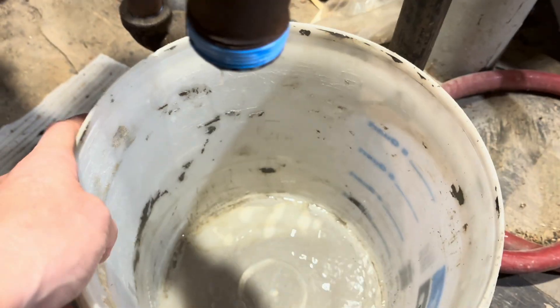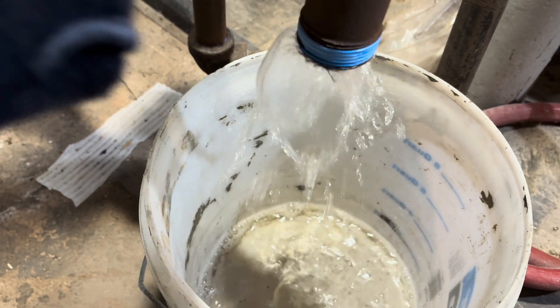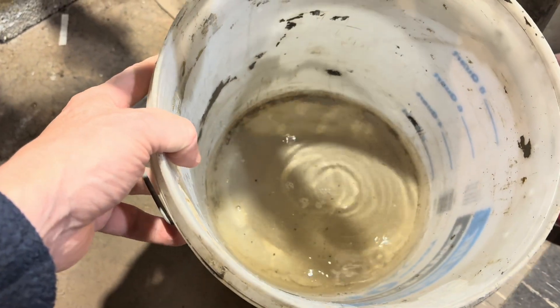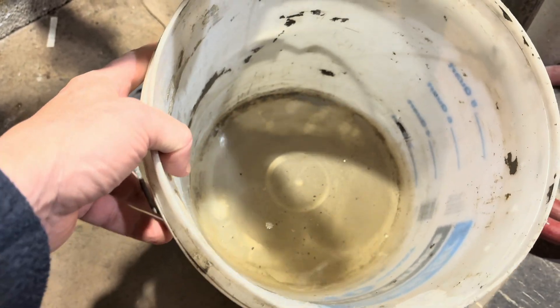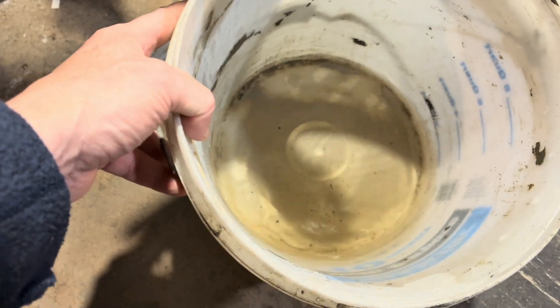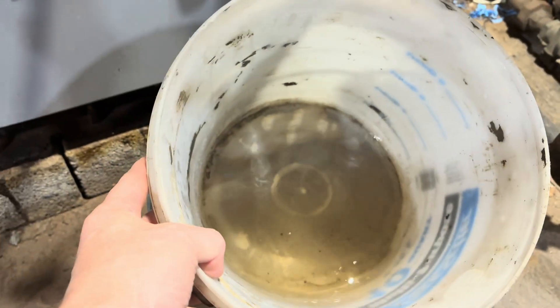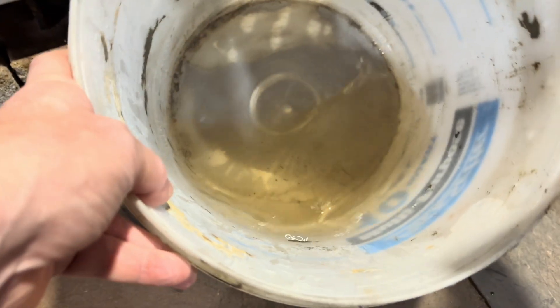Let's try this one. Yeah, totally clear. So I didn't know what this was going to be like, but it's pretty clear to me that my boiler is not rusting at all. There's no measurable amount of corrosion coming out of here. It's a little bit brownish, that's it. But this is by no means anything to be concerned about.